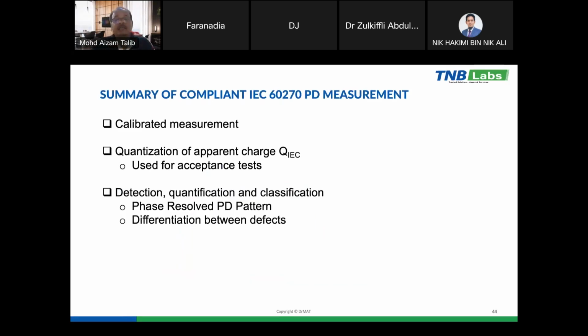So more than 300 picocoulombs means that the equipment has failed the PD testing. Okay, as a summary of IEC 60270 PD measurement, it is a calibrated measurement. If other subsequent tests are done according to IEC 60270, we can compare the measurements. We can quantify its apparent charge, so it can be used as an acceptance test. For example, for factory testing on a power transformer, the acceptance test is 300 picocoulombs. But for site testing, there is no standard yet to quantify the level of PD as an acceptance test. Through this electrical PD test, we can detect, quantify, and classify the type of PD through the phase resolved PD patterns.